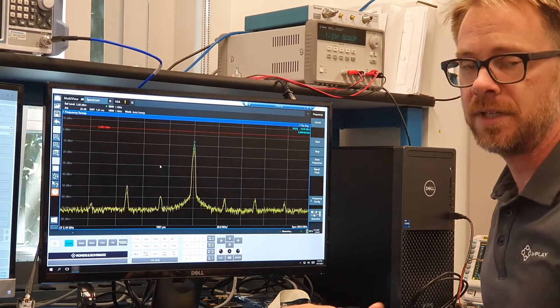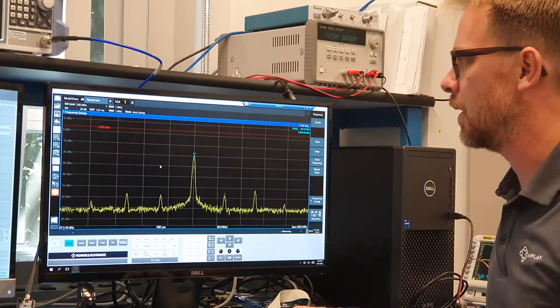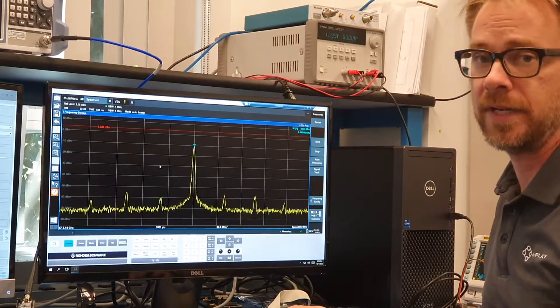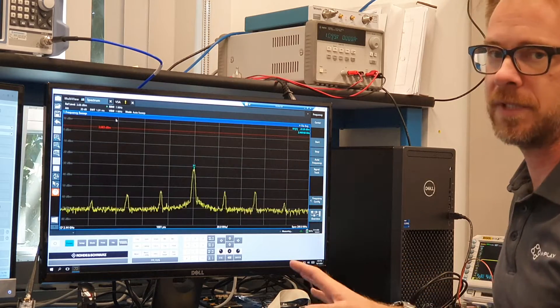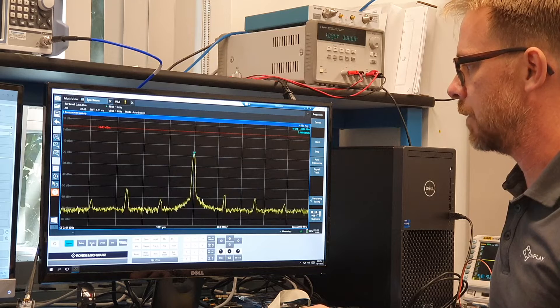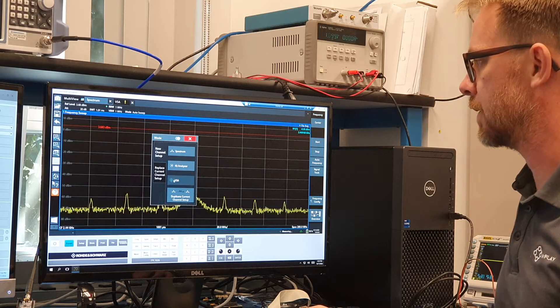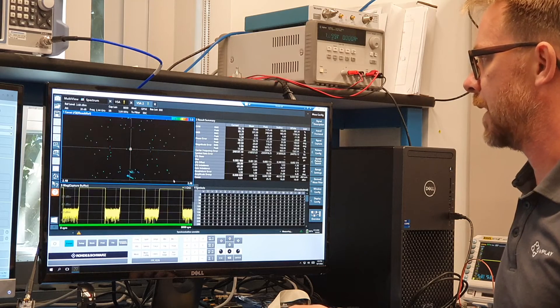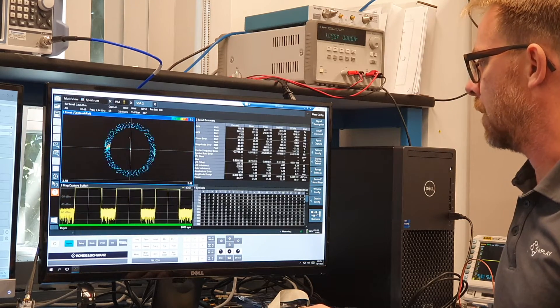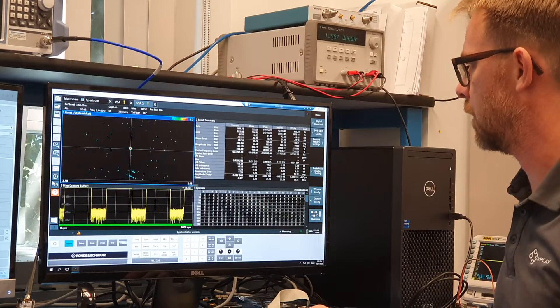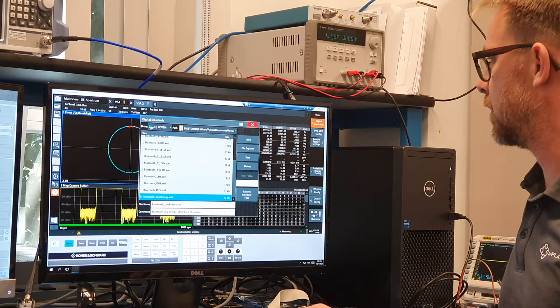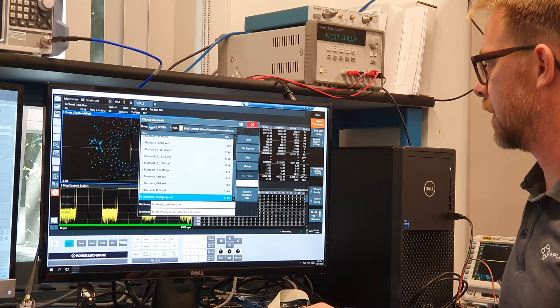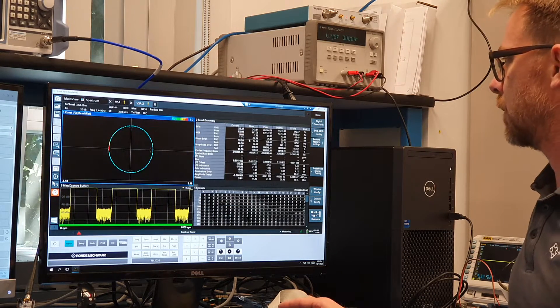In order to demodulate the data and actually analyze the modulation characteristics, we have to use a vector signal analyzer. And that is a built-in tool with this particular spectrum analyzer. So for that, I will go to mode here and select VSA, which will bring up a new VSA window. And I'm going to load a configuration for the BLE standard. So I go to measure and for digital standard, I'm going to select Bluetooth low energy and load that one.